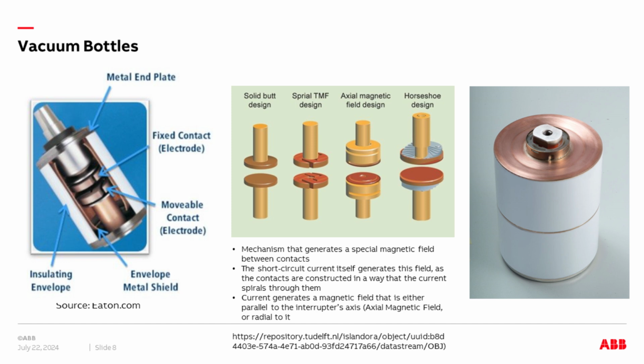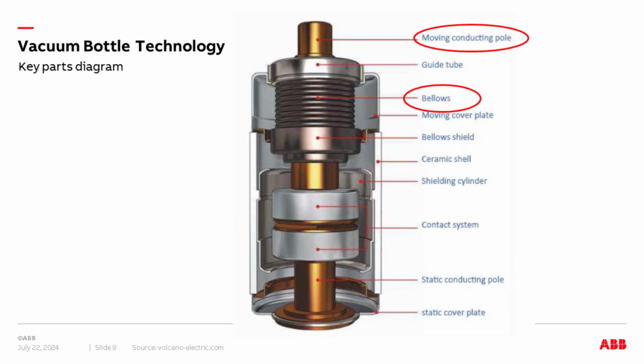The main components inside the vacuum bottle are pretty uniform across the manufacturers, but there's quite a bit of differentiating technology in the contacts, because when the contacts open and the arc is formed, it has to be extinguished. Different shapes of contacts, different metals can actually manipulate the arc to move it apart, to concentrate it, to split it, to allow it to be extinguished more effectively. So there's some examples in the center of different types of technology, and depending on the manufacturer, you will get differences in what those contacts look like, even though from the outside, of course, it looks more like the bottle on the right picture where you just see the housing.